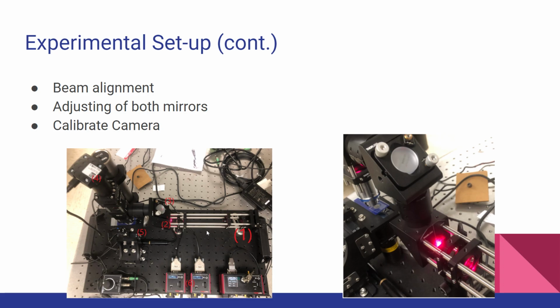And then the beam expander, this section with the metal rods here, was removed and a pinhole was placed over here, and the beam was adjusted with its adjustment screws until it is a fine point shining through exactly the center of the pinhole into the first mirror.